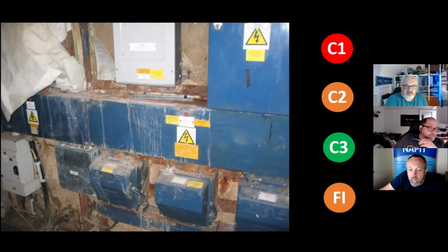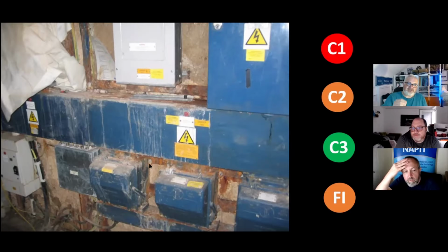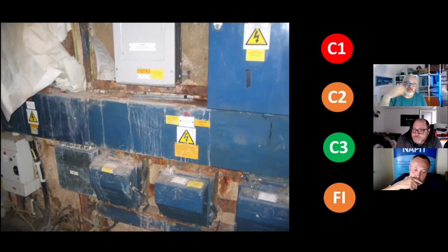I think on that one you can see there's an angle iron frame in the background. There is, yeah, and that's a London Underground switch room, by the way. It was, it's not anymore, it's been gotten rid of. But they used an angle iron frame and mounted all the switchgear on it, and that had corroded to the point where you could see the English Electric switchgear, you could see the connection bolts onto the angle iron. That was the sacrificial part, but because it hadn't been inspected, managed, maintained and intervened, you could have saved yourself a lot of money by taking the angle iron apart and replacing it bit by bit. That was one of the reasons they used this angle iron, because you could intervene if it had corroded and extend the life of the asset. But it had just crept through into the busbars, and the wall had degraded to the point where it was pointless, and that's what you had.